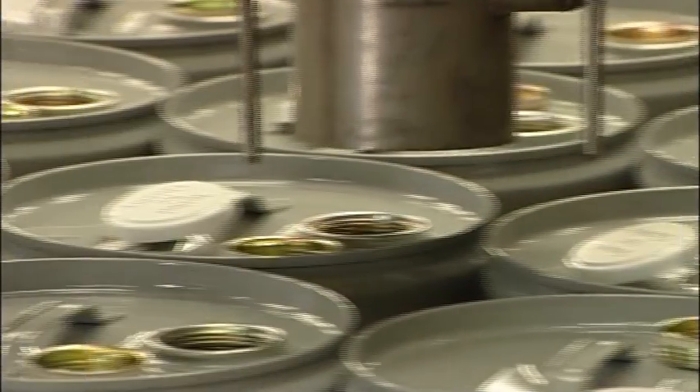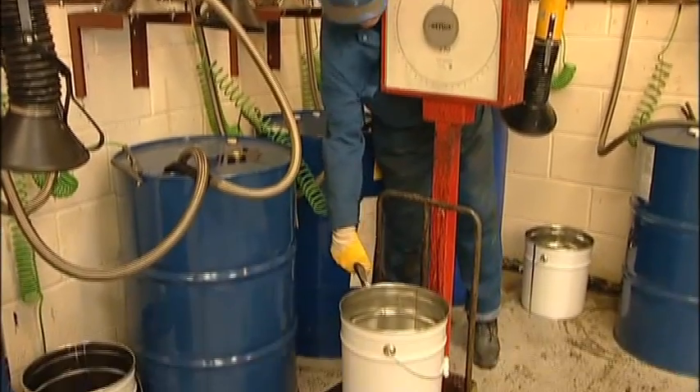We recommend that filling takes place using a lance, whereby the solvent can slowly fill the container from the base, and metal drums and IBCs must be earthed to allow for static discharge.